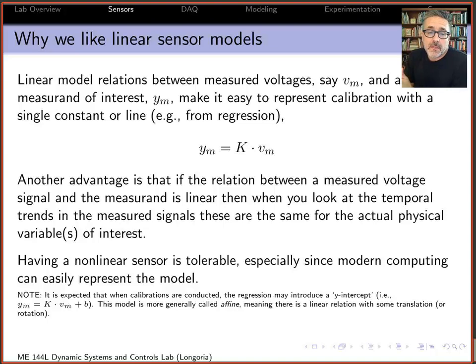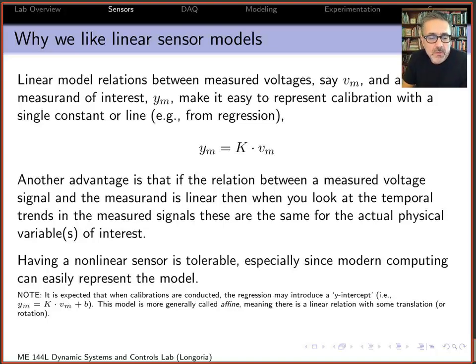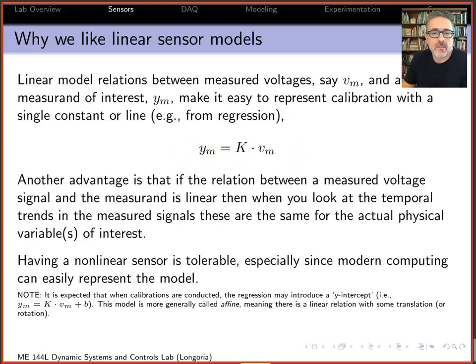Linear sensors are desirable because you can directly relate the measured position to the measured voltage — trends in the voltage directly reflect trends in the actual variable. It's tolerable to have a nonlinear sensor, but then you need to pass the signal through a correction function, which changes what the signal looks like at a glance. Linear sensors require only one calibration coefficient k; sometimes there's also a y-intercept, and while it's convenient to make that go to zero, it's not critical.